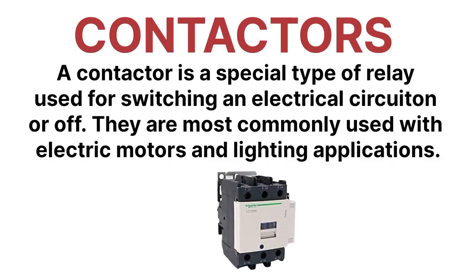A contactor is typically controlled by a circuit which has a much lower power level than the switched circuit — such as a 24 volt coil electromagnet controlling a 230 volt motor switch. This is the main advantage of contactor use.